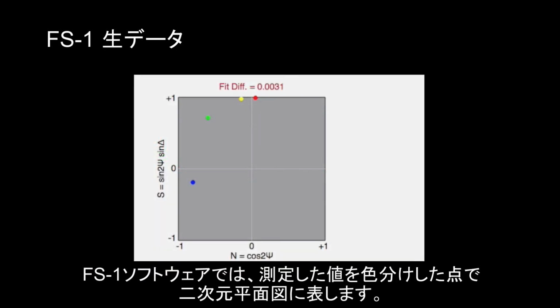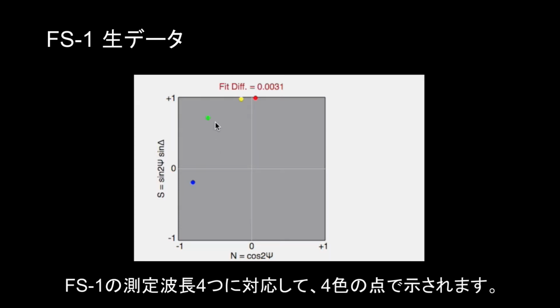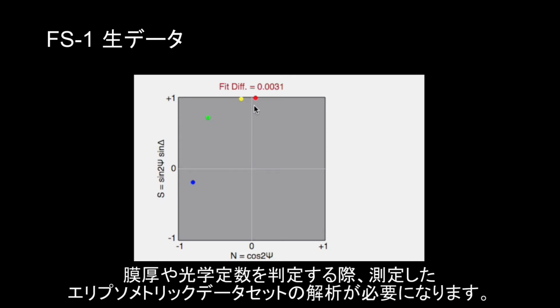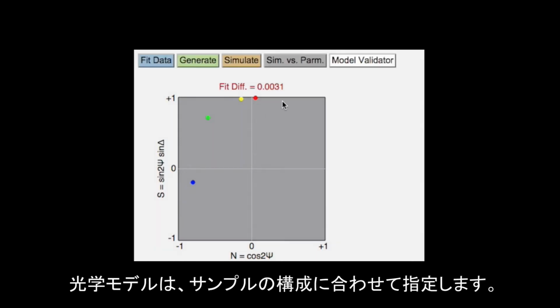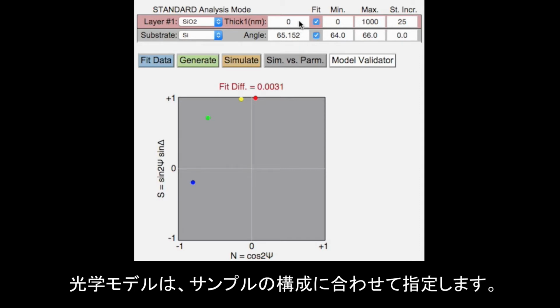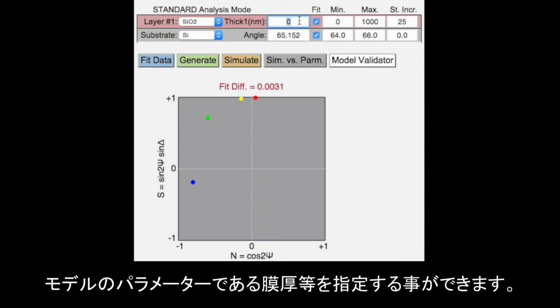The FS-1 software plots the measured ellipsometric data as colored points on a 2D plane. The four colors correspond to the four FS-1 measurement wavelengths. To determine film thickness or optical constants, it is necessary to analyze the measured ellipsometric data set. An optical model is defined, corresponding to the structure of the sample. Model parameters, such as film thickness, are specified.